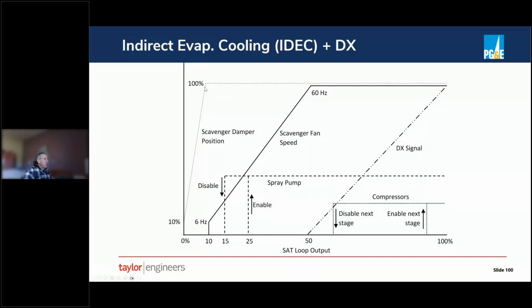So sometimes you have to basically block off the heat exchanger. But once the heat exchanger is fully open, then you turn on the scavenger fan. At some point, you'll turn on the spray, so you can get sort of dry cooling before you turn on the spray. Then once you've got your spray on, your scavenger fan running at full speed, if that's still not enough cooling, then you start to work your DX, right? And if you have big stages, you'll enable a stage at some point, have a disable at some point to minimize cycling of the stages.